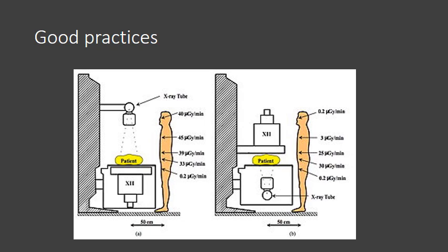itself has protective lead shielding around it that limits scatter and leakage. So the same image with a lead curtain attached on a fixed unit would also lessen the middle exposure. Protective equipment always should be worn, of course, and lead aprons are examined for cracks annually at a minimum, and that's the recommendation by the Joint Commission and the American College of Radiology.